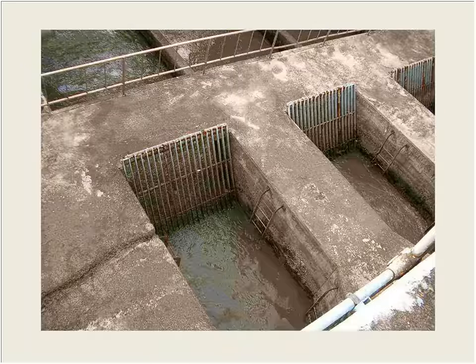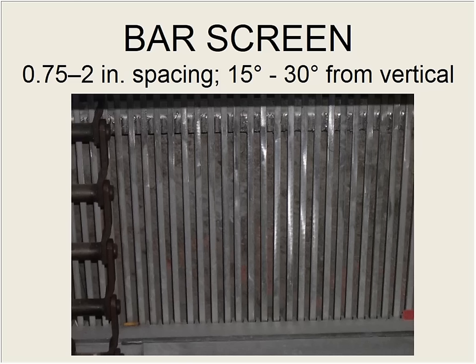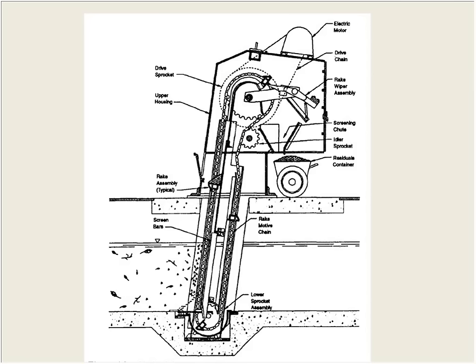So there's a picture of a trash rack, a very crude screening operation. Now, the bar screen, which is a little more common in most plants, is much finer. Quarter inch to about 3/4 of an inch, so it's fairly tight. These are pretty hefty steel bars. They have to take the resistance of flow that comes through the plant.